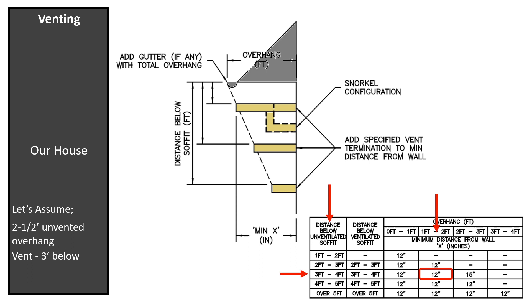This chart will override the minimum distances from the venting charts. If the minimum distance from the wall is blank, you should consider moving the vent to another area or a different wall. The use of the low profile and concentric vent termination cannot be used in these applications because the vent termination cannot be extended.